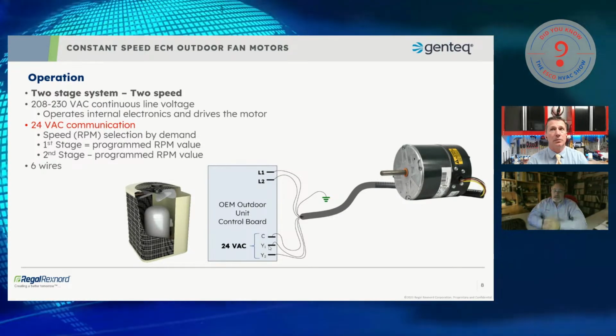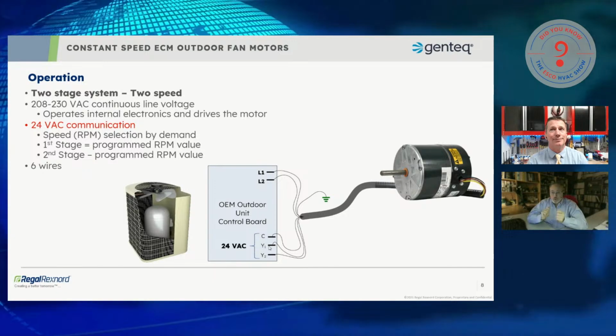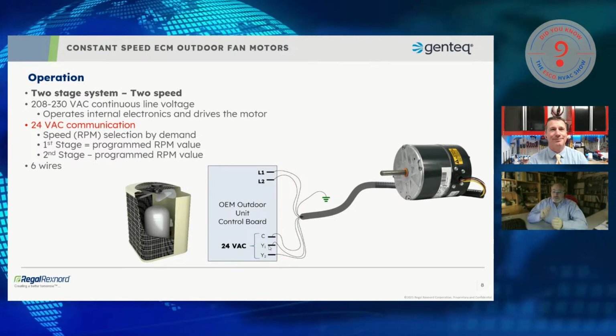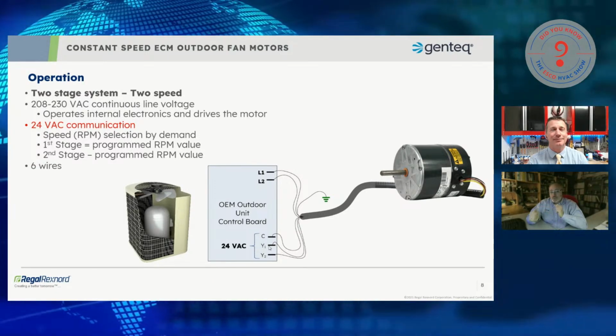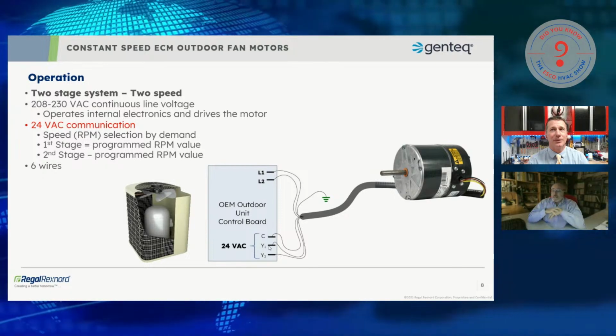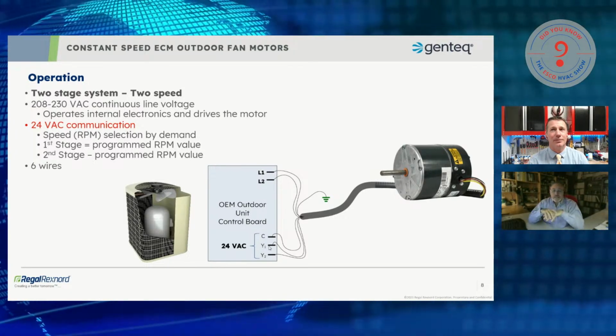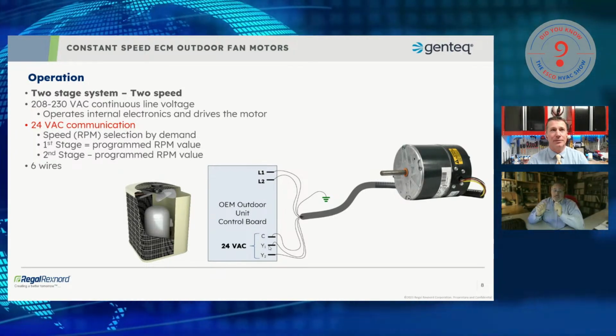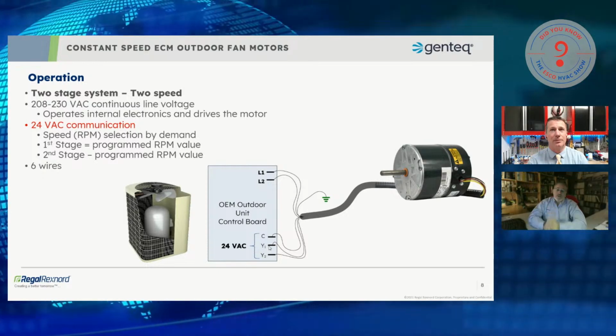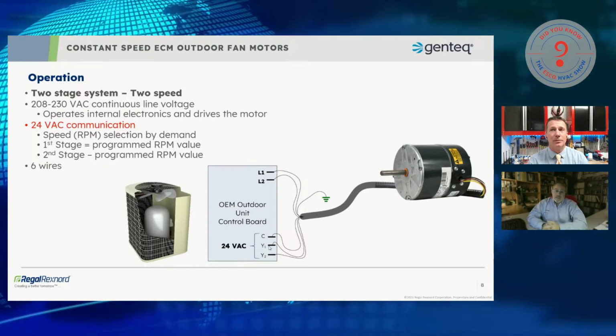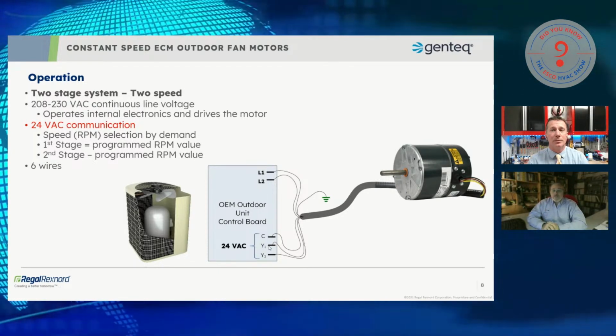We've given the manufacturers the ability to do either or. So you could see them both energized, or you could see it switch from energizing one to the other. This is not like a PSC motor where you had to isolate speeds. You had to turn one speed off to turn another one on. Otherwise, you'd fail the motor. You can have both of them on at once.